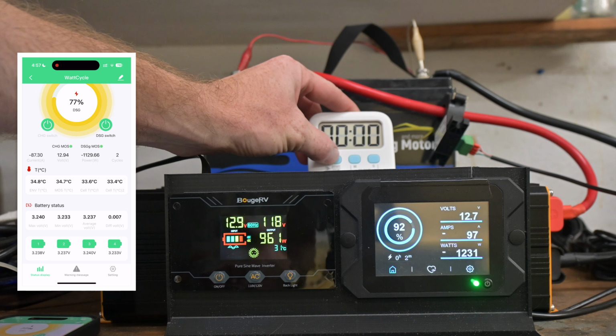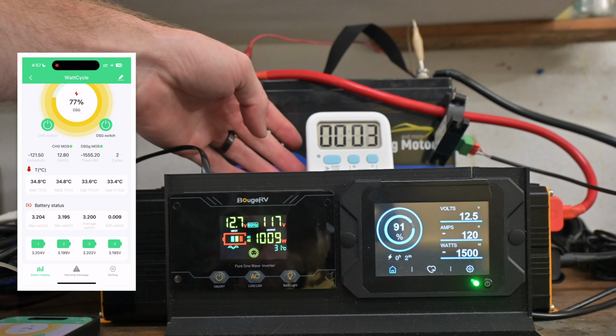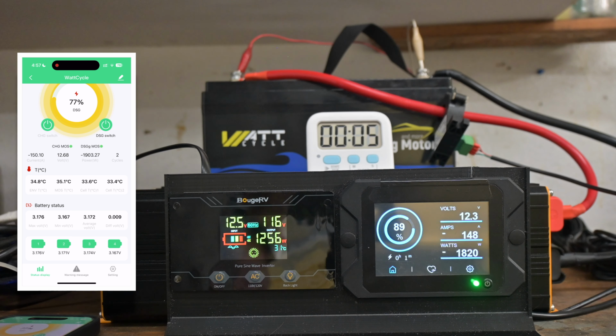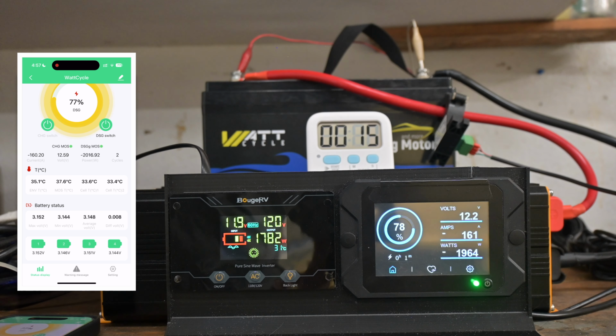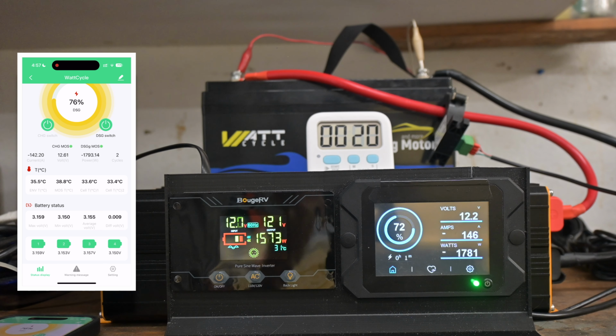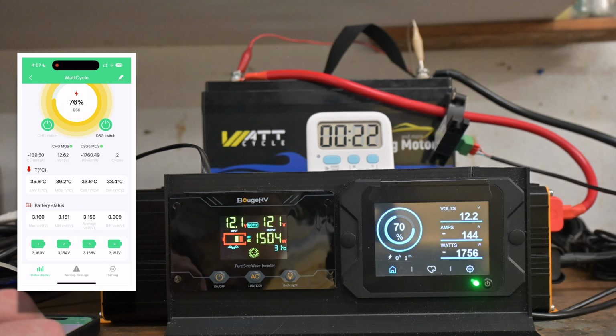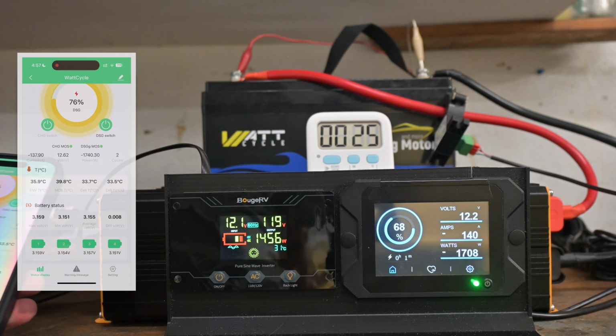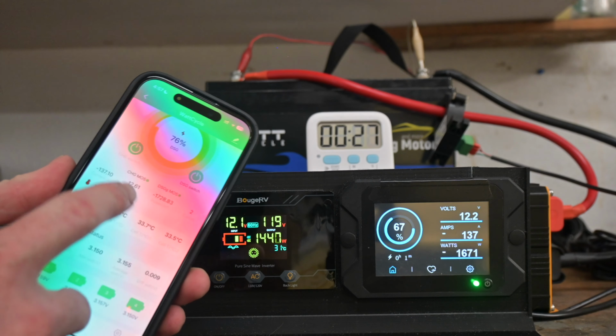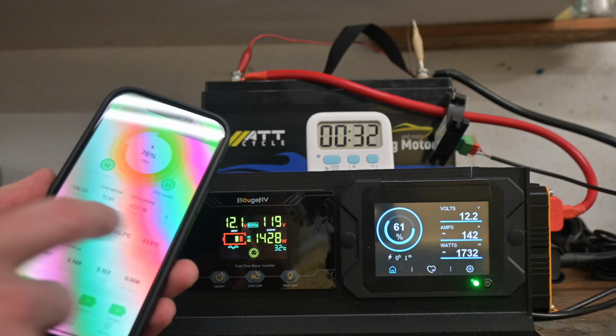79, 97, so we'll call it there at 100 amps. 150, 178, 194, should cool off a little bit from there. We are coming up on 30 seconds over 100 amps. You can see our Bluetooth reading says 136, so it agrees with what we're seeing over here. We're pulling well over 100.